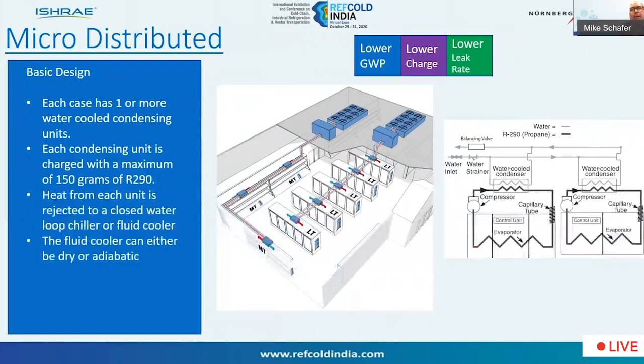So then, as we take this architecture further, from mini racks to a macro system to microdistributed, once again, we're still leveraging those three strategies: lowering the GWP, the charge, and the leak rate. In this case, microdistributed means that we have a case with one or more water-cooled condensing units. Each of the units would be charged with R290 with a maximum charge of 150 grams.